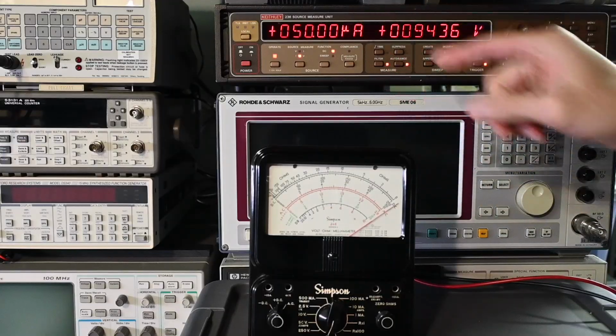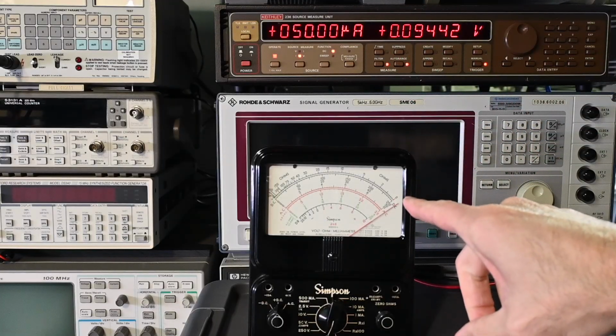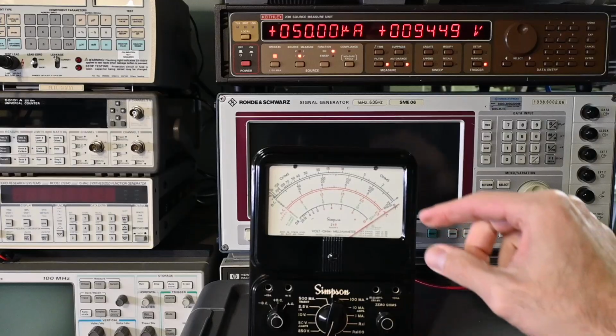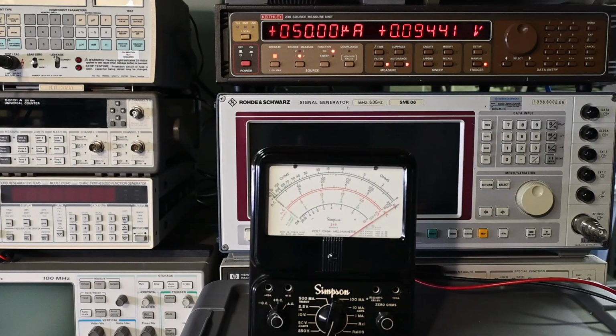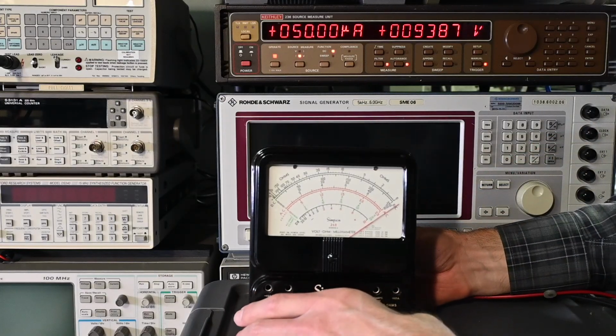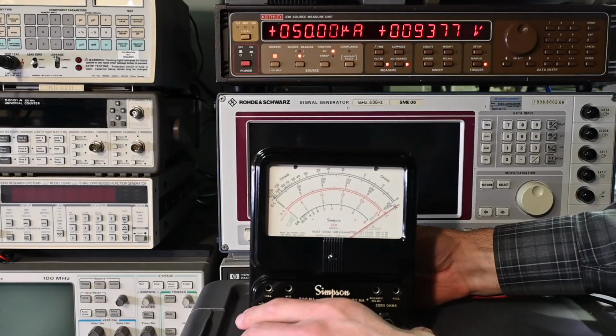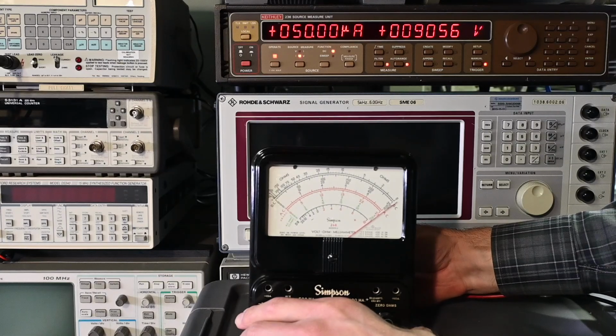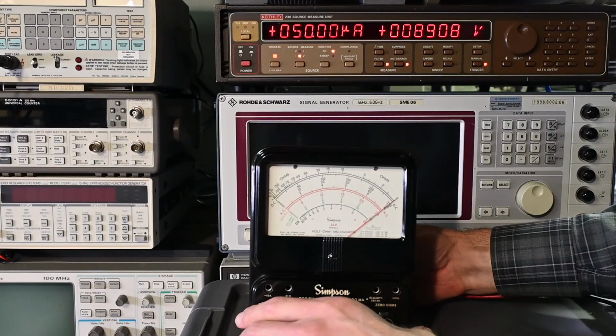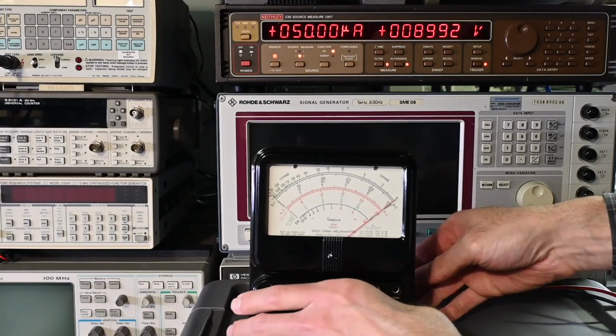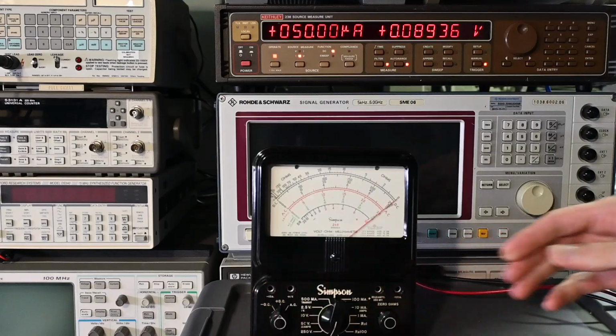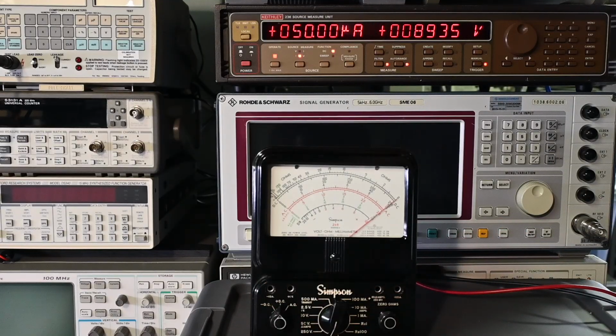So with 50 microamps, you can see that the indication is beyond the last tick mark on the right-hand side. So it's indicating just a little bit too high right now. So reach around here and turn this adjustment. Yep, there it goes. You can see the needle is starting to drop down just a little bit. Right about there, maybe a little bit too far. Right there. That looks really close right there. So yeah, that's looking really good.